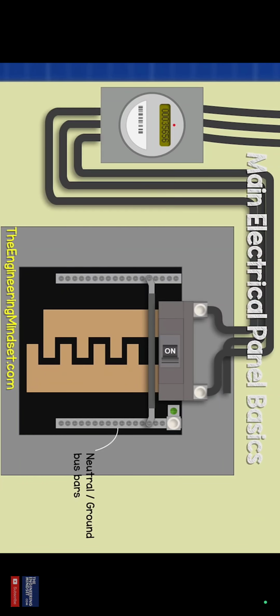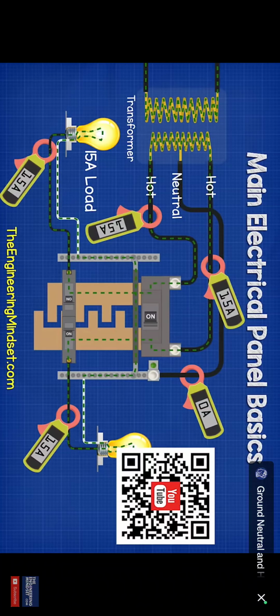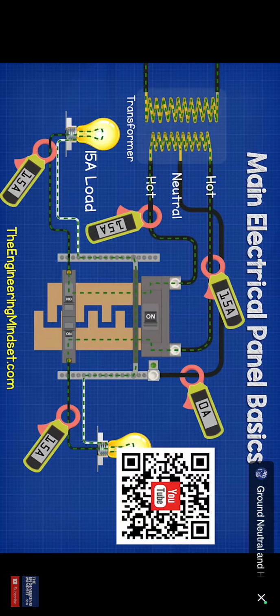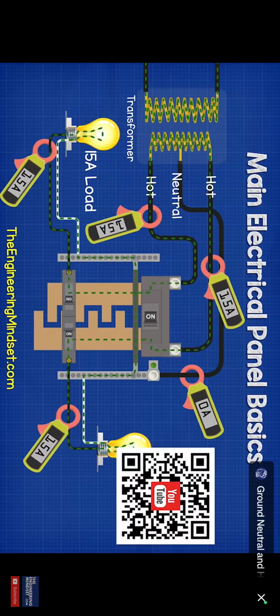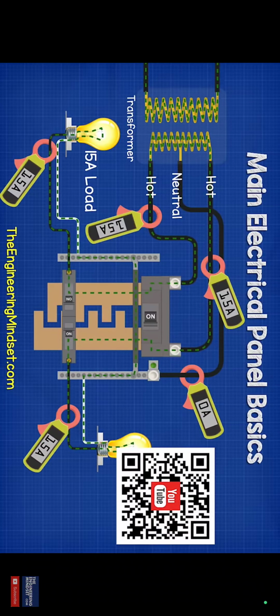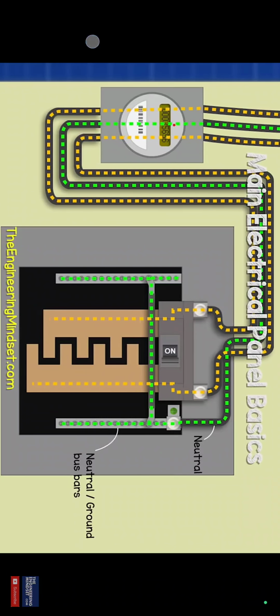From the electricity meter, we will have the neutral wire connected to the lug on the top of the neutral ground bar. Notice the green screw. This is bonding the neutral bar to the metal casing of the service panel. The purpose of the neutral bar is to return the electricity back to the transformer. It does actually get a little bit more advanced than that, but we're going to look at that in a more advanced, complex video. This is just covering the basics.